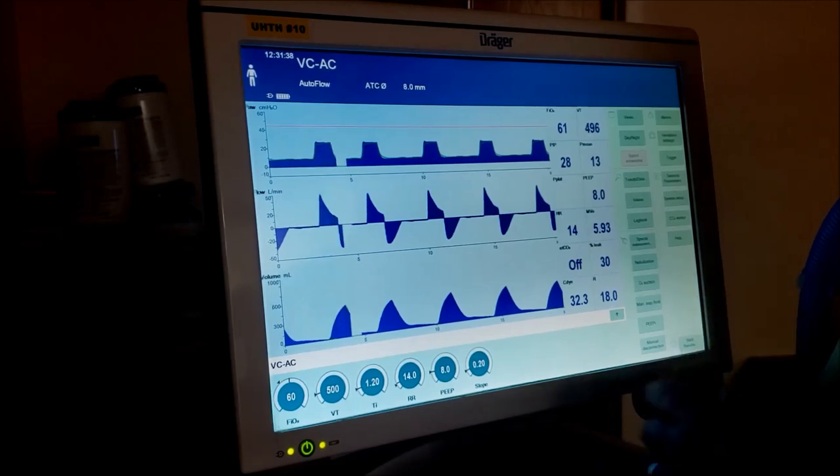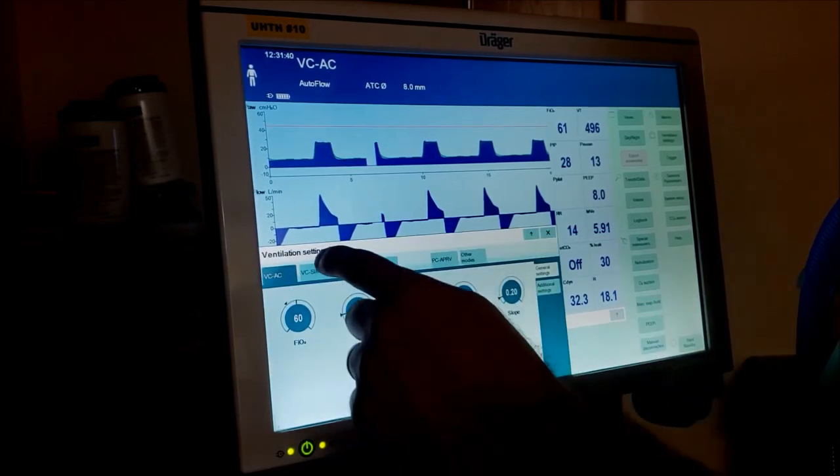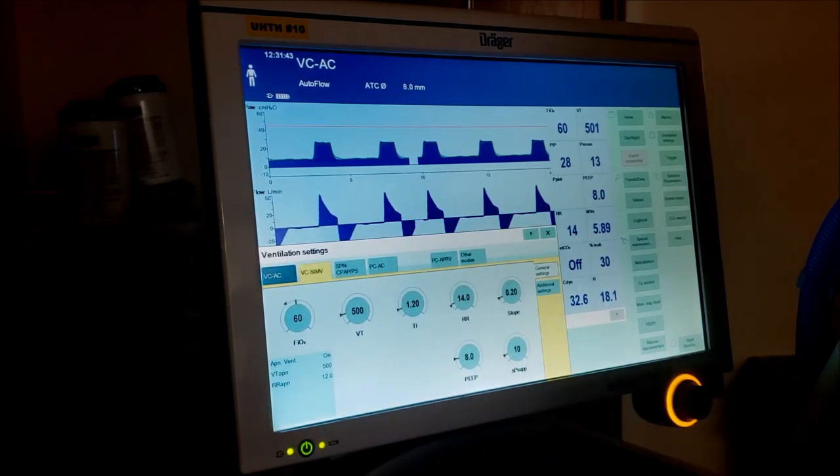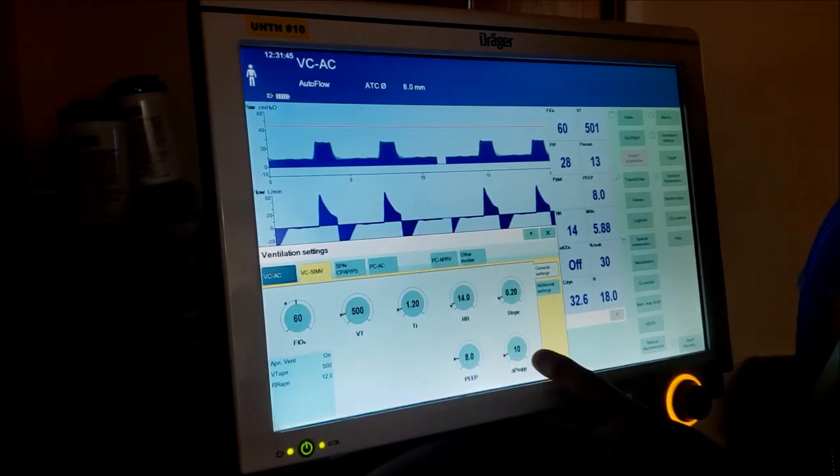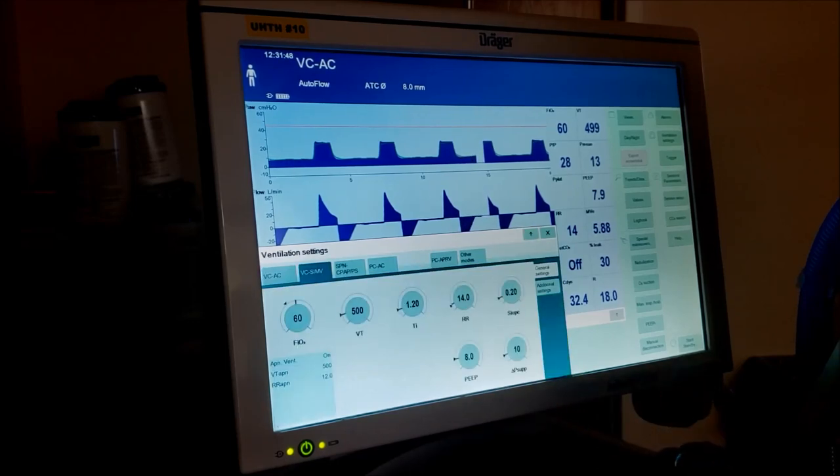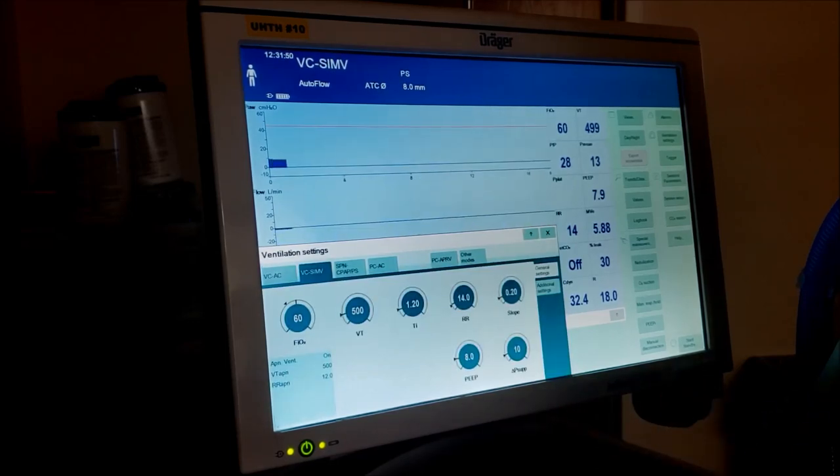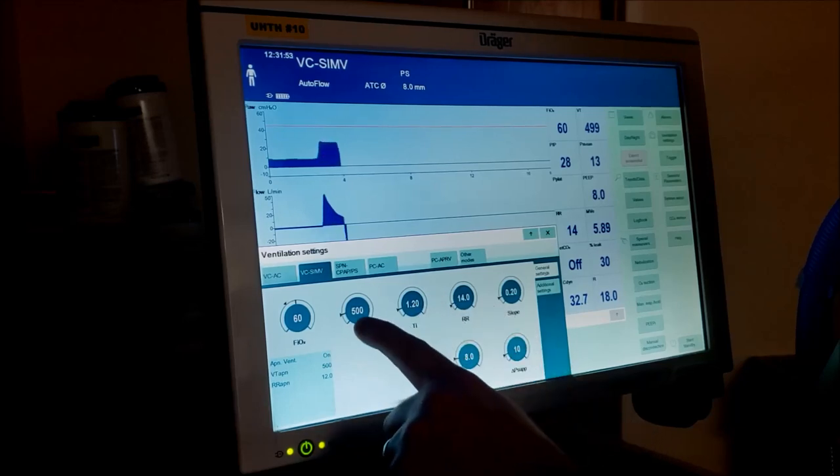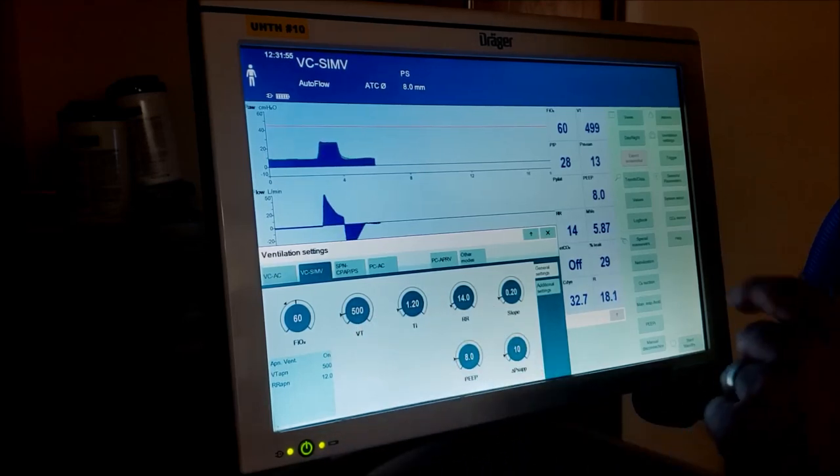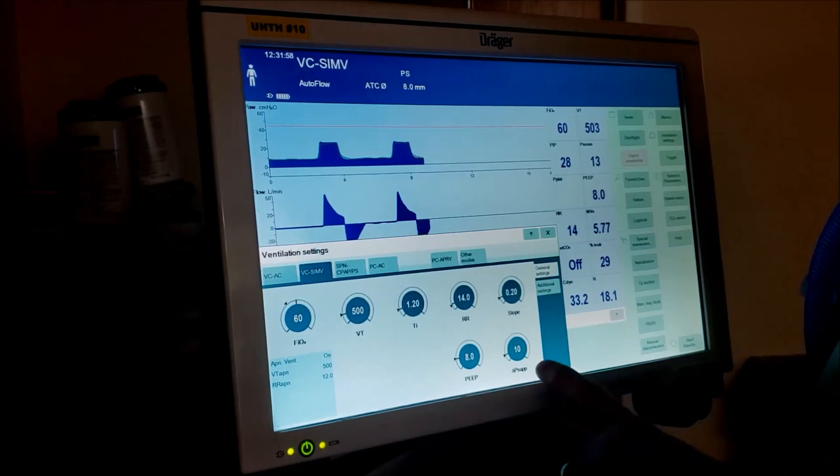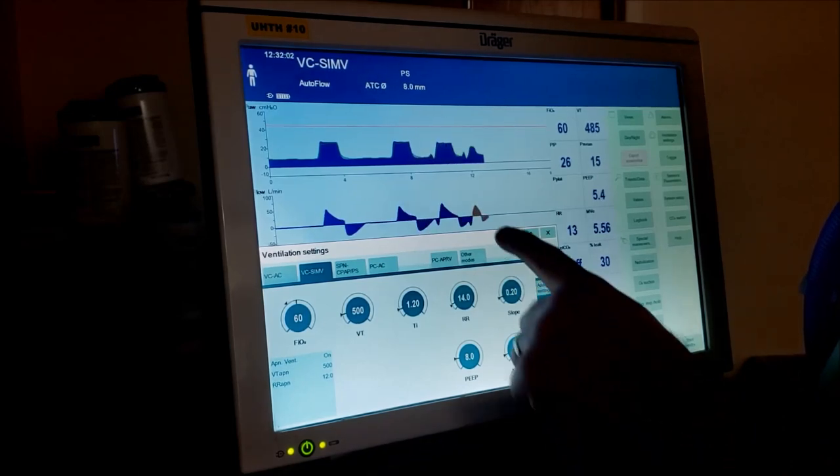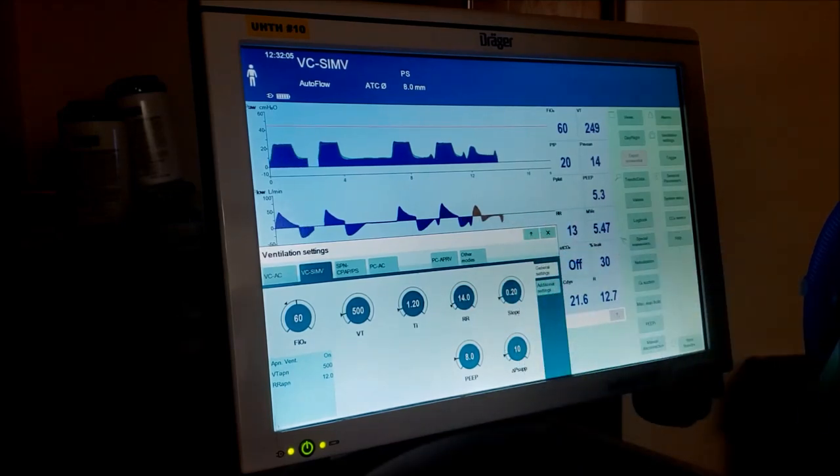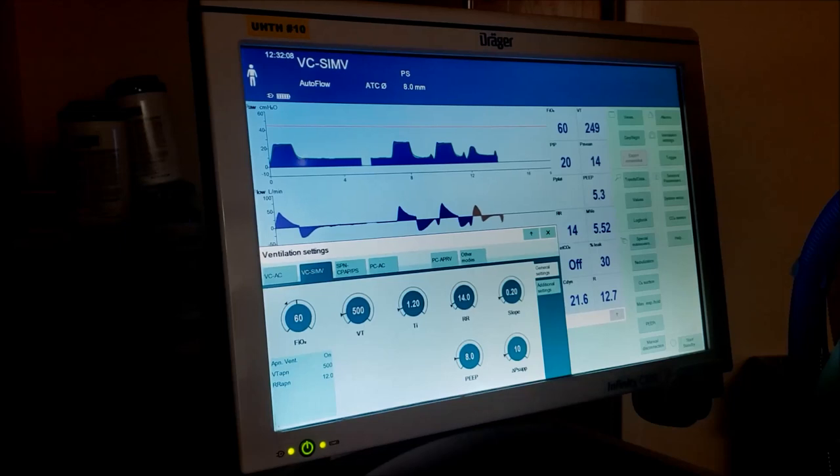Let's look at the next mode. Since this is a quick review - SIMV. If I go to SIMV, you see we added one more number on there. That's pressure support. Let's go to SIMV. We're going to turn that on. What this means is the patient is going to get 14, 500 per minute. But when they take their own breath, it's going to be augmented by this pressure. You see that it's not a full breath, it's just assisted. And you can see that assisted breath right there.